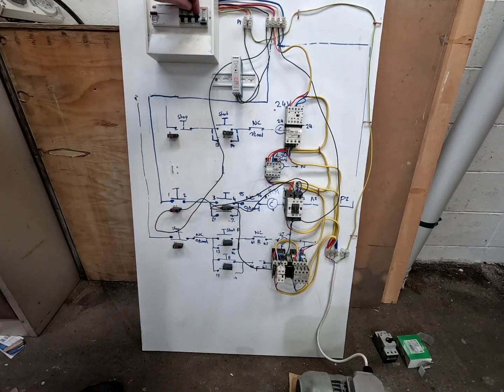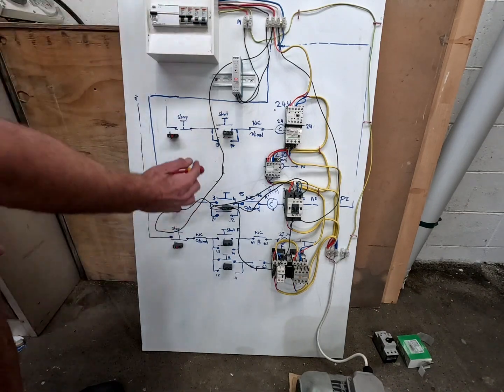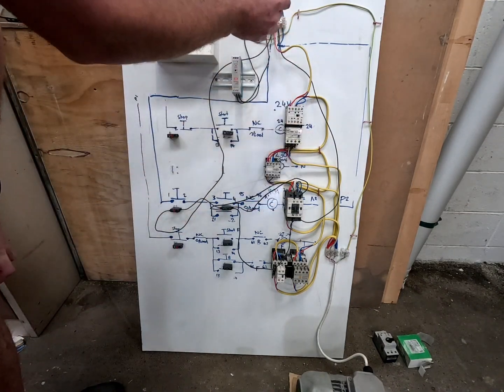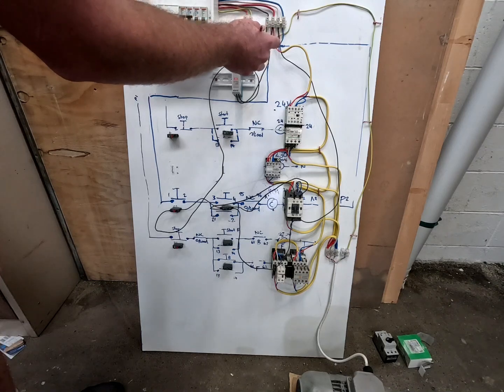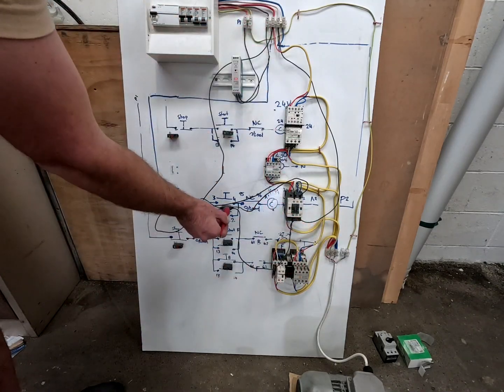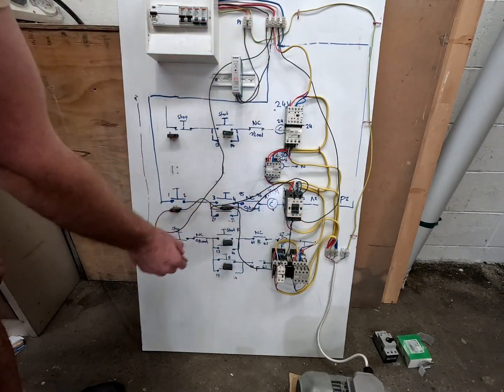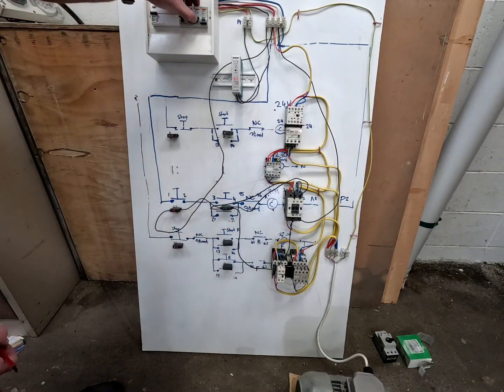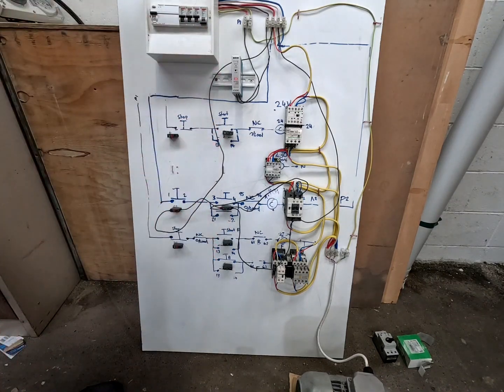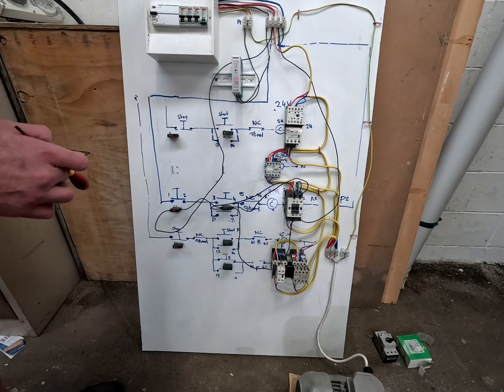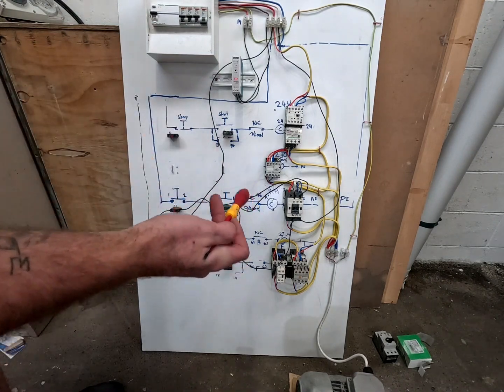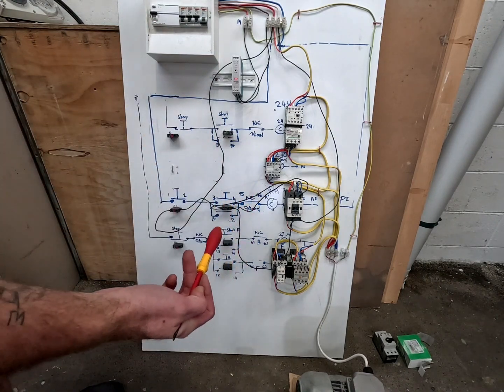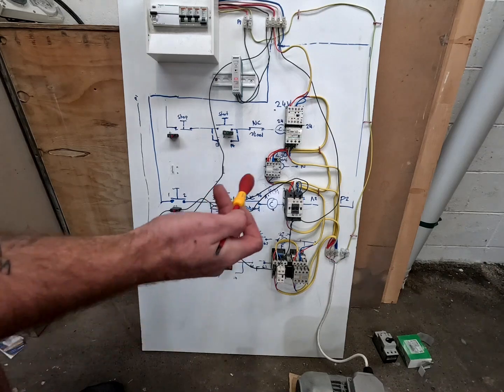But if you had the blue phase not on, this will start because we still have our two control circuit phases, but we don't have the third motor phase. See how much smoother it runs with all three phases? So there's two little tips for you if you are having trouble with three phase contactors.